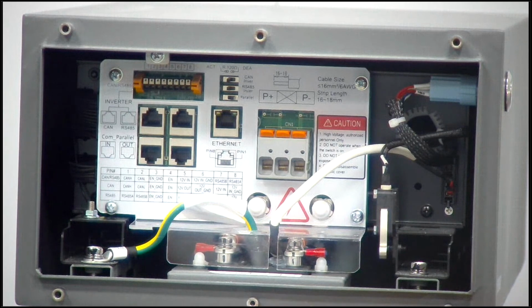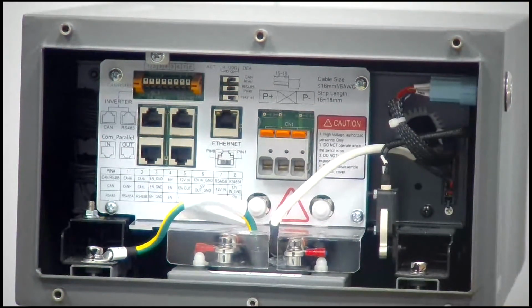First, of course, you have to check the configuration through the BConnect app to check whether you have put the right numbers for the towers, and chosen the right inverter and battery type. Then if that's all correct, you have to open the BCU side cover to check whether you're doing the right cable connecting.